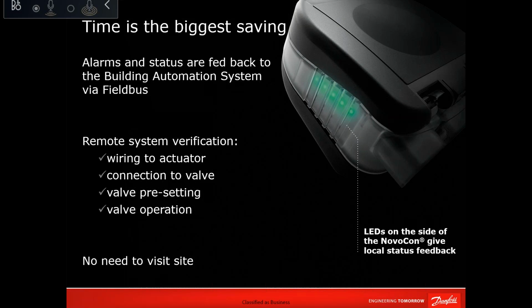from Danfoss at the factory to be a standalone delta T manager, which means I can set the Novocon to respond to your room thermostat up to the point where your delta T is less than the design value. Let's say I tell the Novocon to open and close based on the room temperature. The moment the delta T drops to less than 7.5 or less than 8, you disregard the thermostat control and you control on your own to maintain that delta T. Once it is maintained, then you release the controls back to the normal local analog or thermostat control.